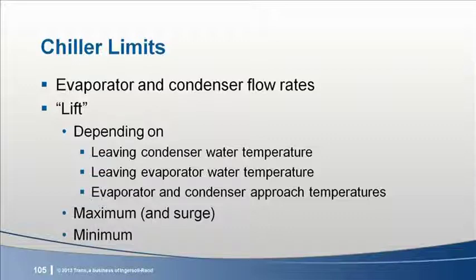On the other end of the spectrum, all centrifugal chiller manufacturers have a minimum lift requirement. This limits how far the tower water temperature may be depressed or chilled water temperature may be increased. From the literature we've seen, these requirements seem pretty similar for all the manufacturers.